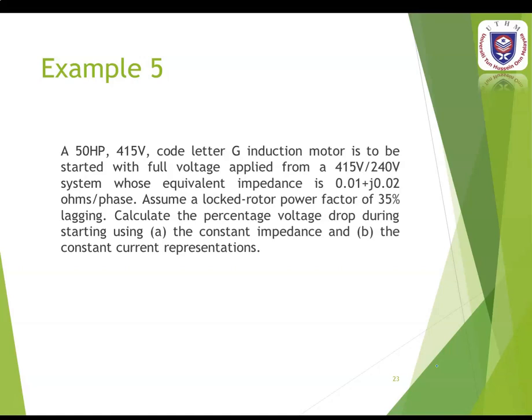Looking at Example 5: a 50 horsepower, 415 volt, code letter G induction motor is to be started with full voltage applied from a 415 volt to 240 volt system whose equivalent impedance is 0.01 plus j0.02 ohms per phase. Assume a locked rotor power factor of 35% lagging, so power factor is 0.35 lagging. We have to calculate the percentage voltage drop during starting using two methods: constant impedance and constant current.